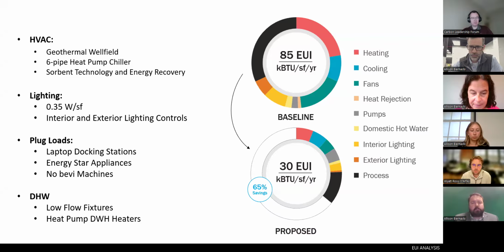We had a geothermal well field and used a 6-pipe heat pump chiller doing both heat recovery and highly efficient heating and cooling. We also did an interesting outside air and ventilation strategy that actually scrubs the air, reducing how much air we need to bring into the building from a ventilation standpoint, which saves a lot of energy from a conditioning standpoint while also helping indoor air quality.